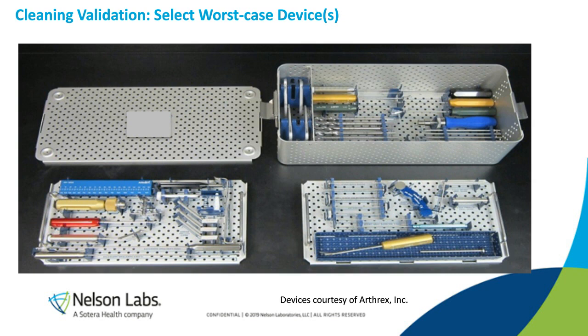But there's devices that include lumens, include ratcheting areas. There's also devices that may include some knurled areas, inaccessible areas, but there's also devices that will be very simple and easy to clean, like simple metal devices that don't have any challenging features. And so we have to look at every device and compare it to the others and determine which would be the worst case device for the cleaning validation.